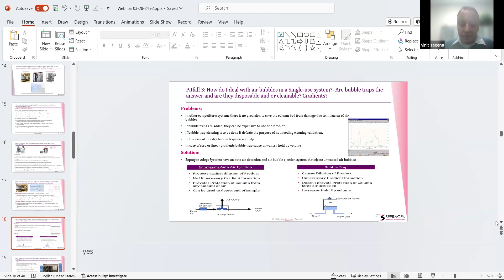So Sepragen systems have unique auto air eject systems, so we can measure the size of the air bubble and dynamically eject it from the system. So no air enters the column, but you're doing it without introducing hold-up volume in the system, which is causing unnecessary gradient formation or product dilution. We can sense the air bubble and eject it out of the system in real time. So it's a more elegant solution of dealing with these kinds of issues. So checking out how somebody's system deals with air bubbles is very important.